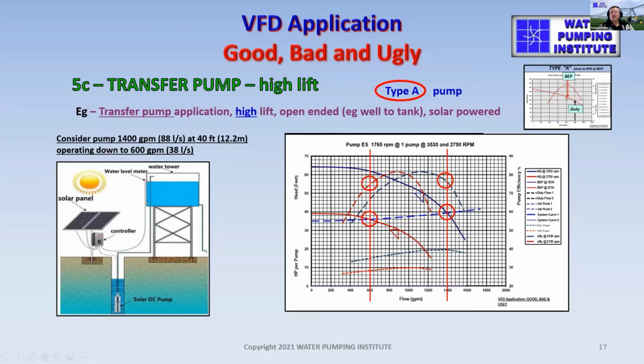It's on the falling side of the right hand side of BEP, and when the pump is operating at its slowest point, it has followed the best efficiency point over the peak and down the other side. So pretty much the starting and finishing points are as low as it can go. Everywhere in between, it is a higher efficiency. So I'd regard that as a very good application.